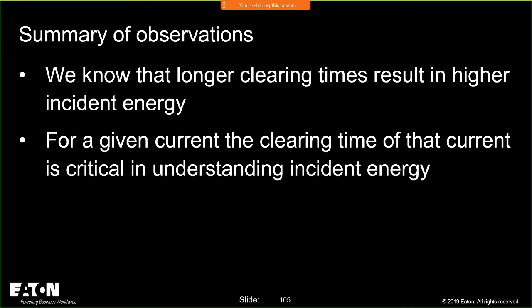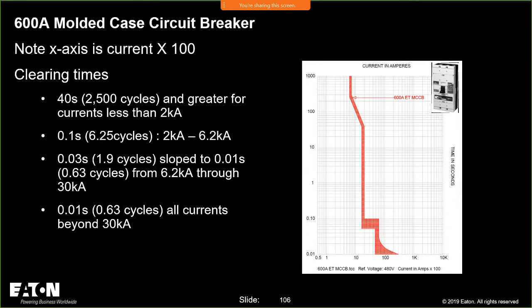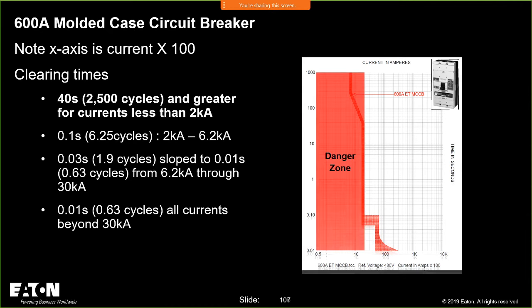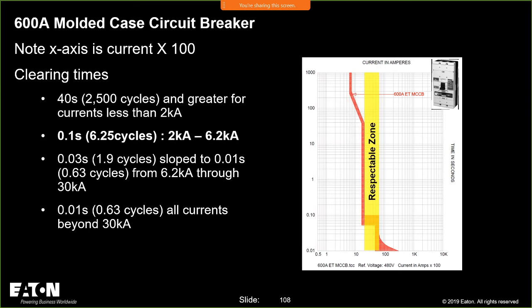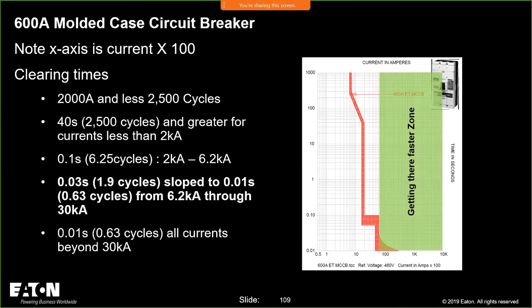And you know the clearing times. The faster clearing times are going to give us a lower incident energy. And again, it's all about that trip curve. We're going to cover the breaker basics and understand what comprises how this is all constructed next week a little bit. Again, the higher the current you go, the faster the clearing time. The faster the clearing time, the lower the incident energy.